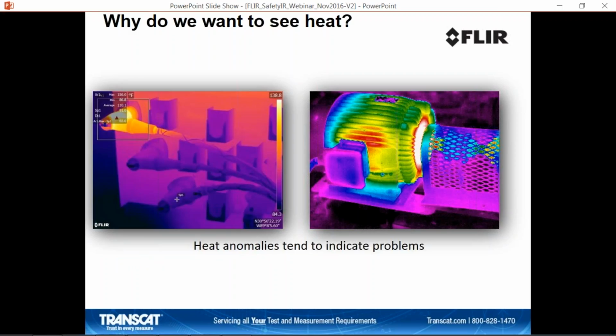So why do we want to see heat? We're looking for anomalies. If you look at a motor and see the bearings heating up, you're able to tell just by looking at the image in a split second if those bearings are an issue. You're also able to look at the temperature on screen at your specific target or pixel point and find out how hot that target potentially is, i.e. how bad the problem is. Looking at the left-hand side, on those 3 plugs, those 3 phases, we could see the top phase is much hotter than the other two, which indicates a problem. Without a thermal imager, we wouldn't know if that was an issue.